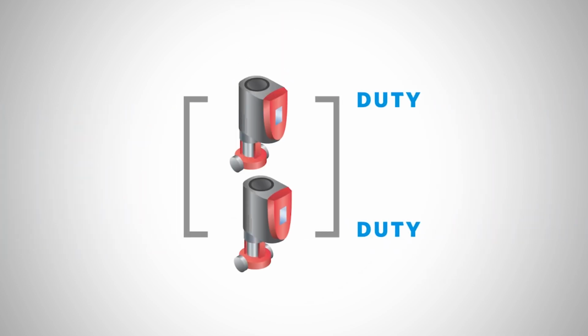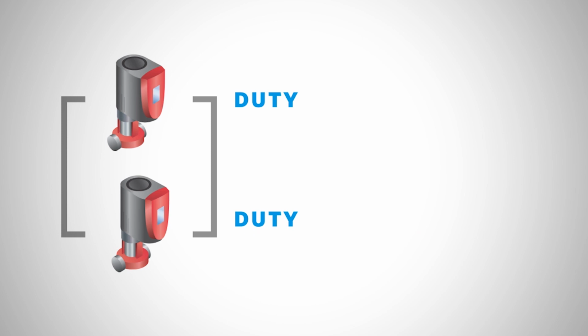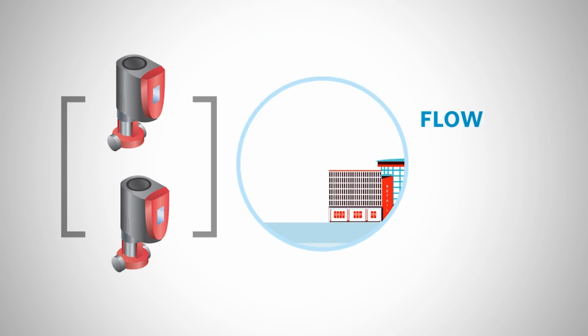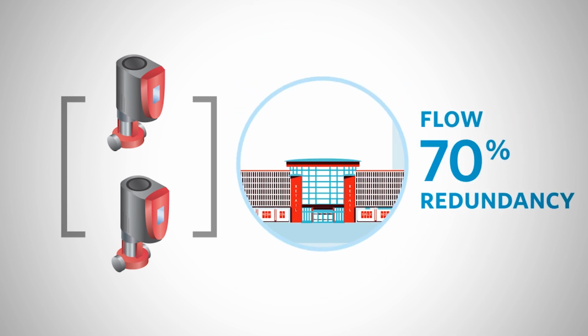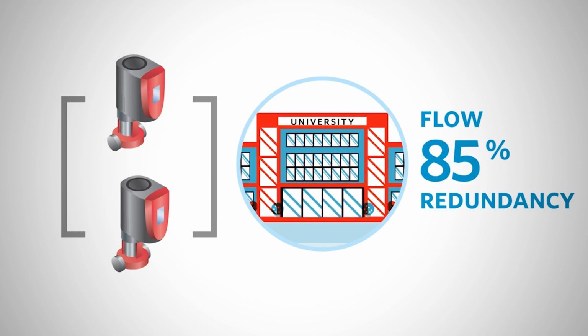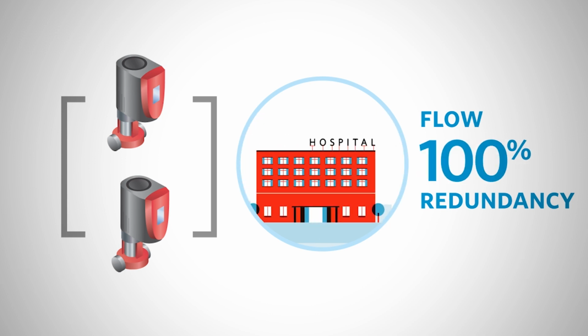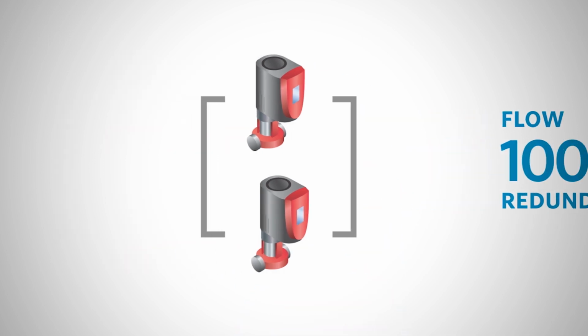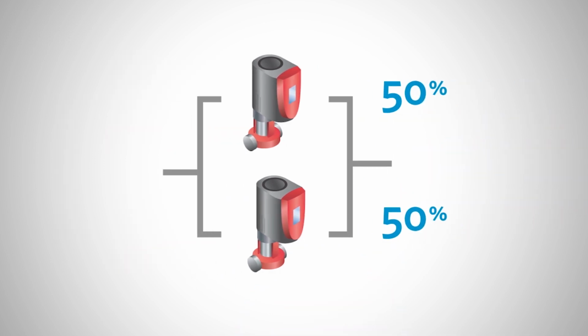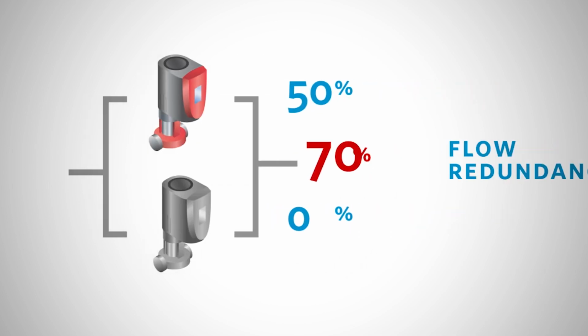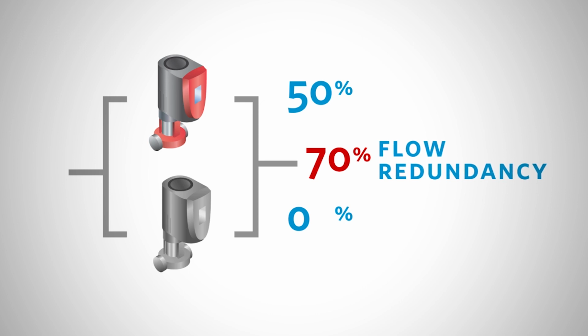Because HVAC systems function at part load for the vast majority of operating hours, it can be more cost-effective to design a pump installation using multiple pumps in parallel instead of a duty standby configuration. Based on the function of that building and the importance of guaranteed uptime in serving that function, the pump selection and sizing can reflect an appropriate level of redundancy. For example, a flow capacity split of 50-50 would result in each of the two pumps being sized for 50% of the design flow. If one of the pumps is offline for service, the remaining pump could still provide as much as 70% of the design flow rate.